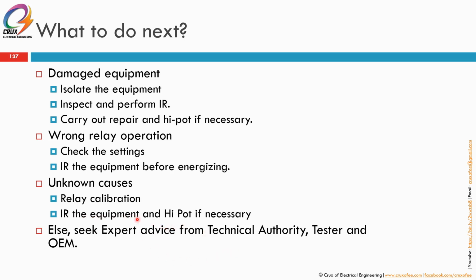If you are not sure what to do next, for example you've already checked everything and you are still unsure whether you want to energize or not, please seek expert advice from the technical authority of your plant or your company, or from your tester, and of course from the original equipment manufacturer for the switchgear or the motor. So that is all on what to do after a relay trips.